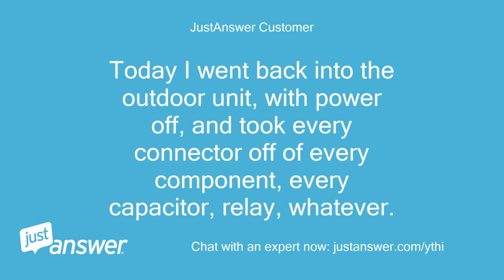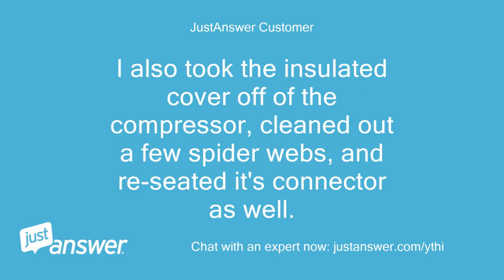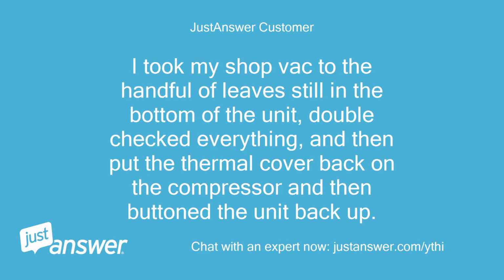Today I went back into the outdoor unit, with power off, and took every connector off of every component, every capacitor, relay, whatever. If I could reseat a connector I went for it, if it was a screw connector I loosened and retightened it including the ground. I also took the insulated cover off of the compressor, cleaned out a few spider webs, and reseated its connector as well. I took my shop vac to the handful of leaves still in the bottom of the unit, double-checked everything, and then put the thermal cover back on the compressor and buttoned the unit back up.